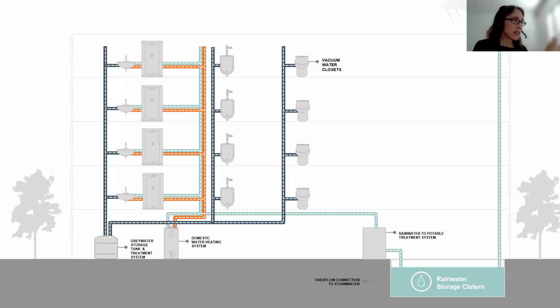This is that same schematic with the gray water system added in. We collect water from the lavatories and showers that goes into the storage and treatment system for gray water, and then that's pumped out to the urinals and vacuum water closets. Those vacuum water closets use a very small amount of water, and the urinals are urineless, except they flush every 72 hours to clean things out.